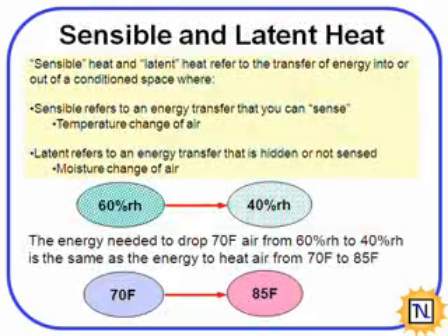Now, within these homes, I was talking about the ventilation and moisture management. There's two components to conditioning a house. You have sensible load, which most of you are familiar with, just changing the temperature. But then you also have the latent load, and that refers to this moisture. And both become very important. Conditioning a house going from 70 to 85 degrees takes the same amount of energy as reducing the relative humidity from 60 to 40% at 70 Fahrenheit. So there's a lot of energy that's going to be needed to do this moisture management as well.